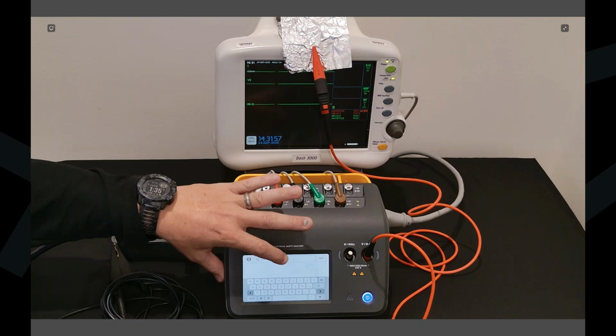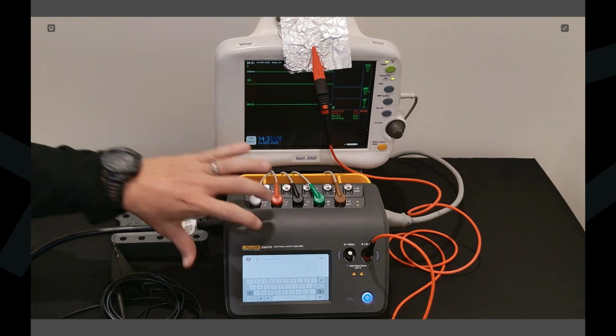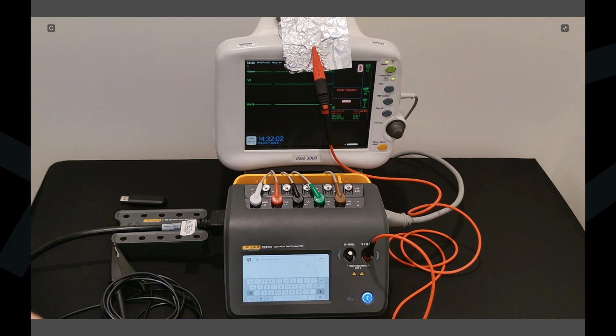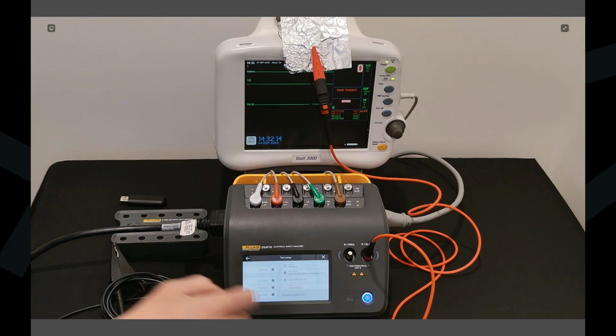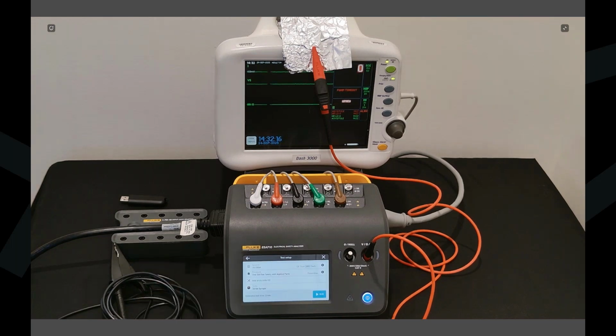Just a quick electrical safety. You can scan your device, again, using your barcode scanner. Scan your device. And now let's run a quick electrical safety with applied parts. Another cool thing I like to do is you can do both, because not all electrical safety devices will have applied parts. So you essentially could set up two if you wanted to. You could have an electrical safety with your applied parts, then an electrical safety without your applied parts, and that would cover a pretty broad spectrum of anything that you would want to do.